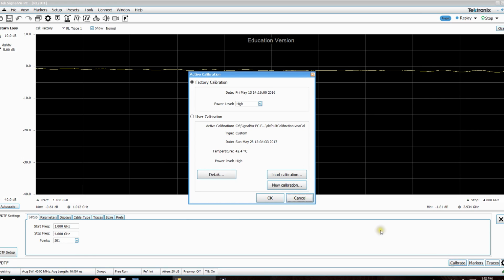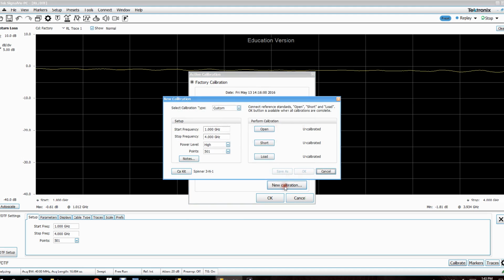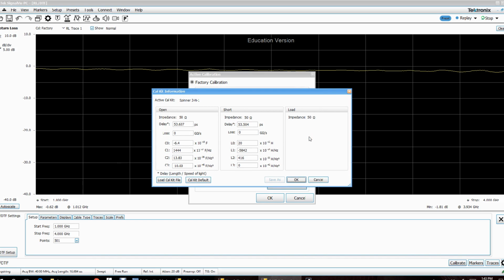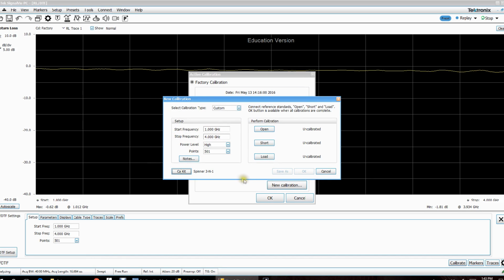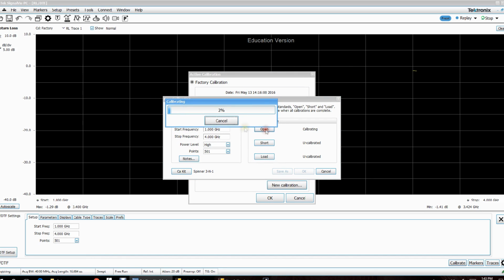Let's go and calibrate here. Now for the calibration, you can use the factory calibration or the user calibration. Let's do a new user calibration there. All the settings are already here. The cal kit parameters can all be entered, so it's a full-fledged calibration. There are no shortcuts here, but I'm not going to enter these parameters here because first of all, I don't know exactly what they are for my calibration kit, and for our purposes, we really don't need to worry about that. So let's do an open calibration here.